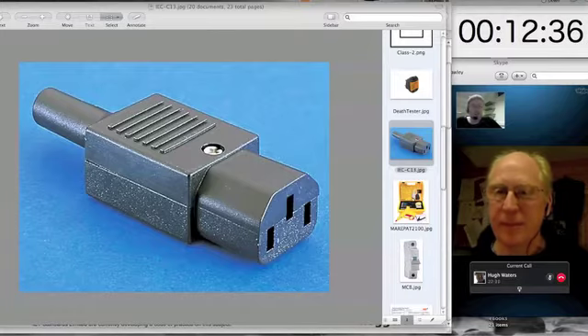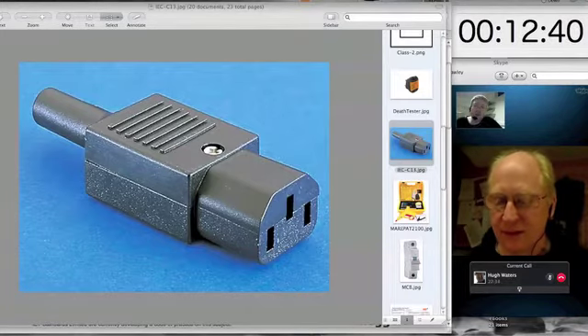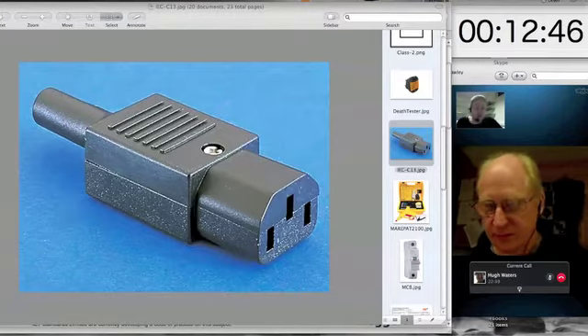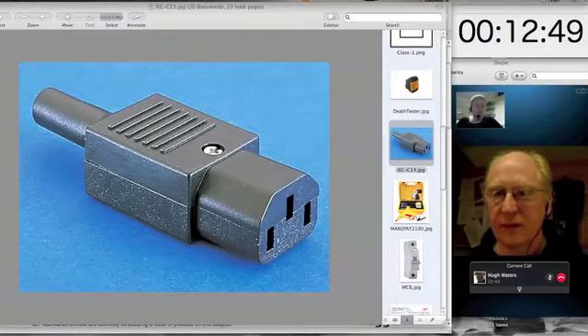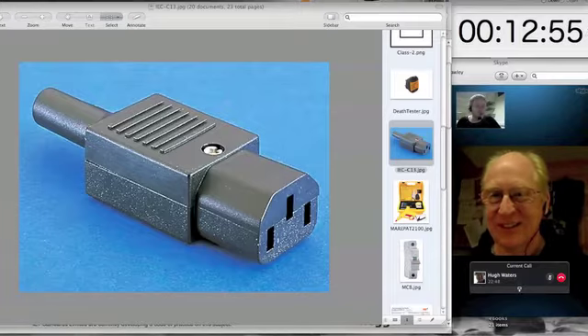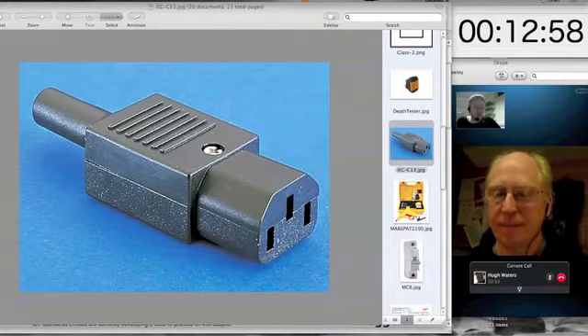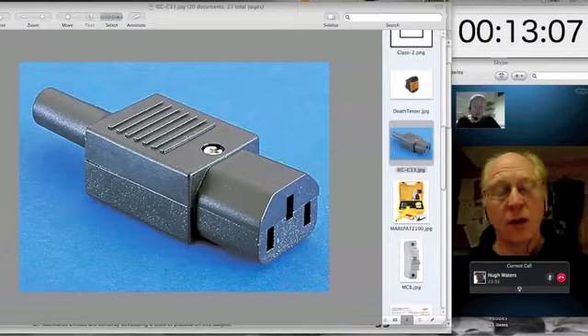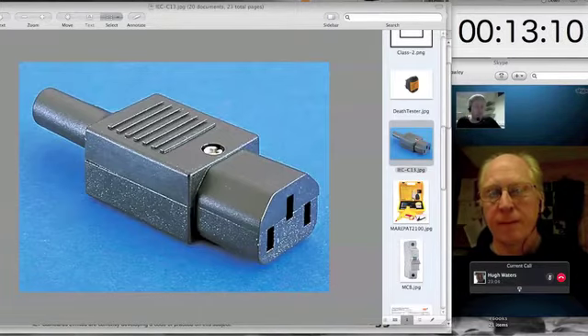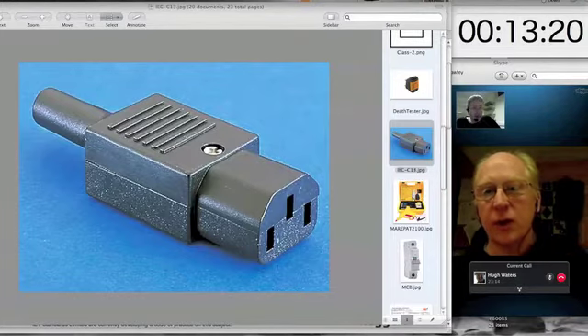So absolutely. So fuses are the kind of old school method of causing that, and you typically still find those in plugs, in the distribution strips at the top of equipment cabinets, but once you get back to the distribution board that's feeding the machine room, that's feeding your house, you won't find fuses anymore. You'll find miniature circuit breakers, because as a user serviceable part, having fuses in the main incoming fuse board was never considered a great idea, and it's much better to be able to just reach up and flip the breaker back over, and it works in exactly the same way. It's a bimetallic strip. It's a thermal device, and when too much current's pulled through it, it flips and knocks the MCB out. Is that actually still true right at the incoming point in your facility of mains?